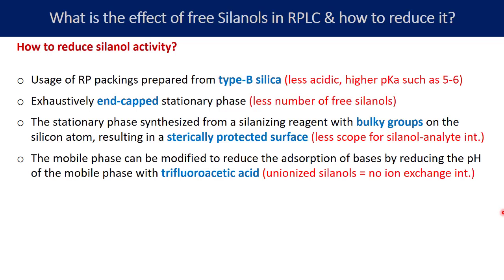Fourth, the mobile phase can be modified to reduce adsorption of bases by reducing the pH with trifluoroacetic acid. At very low pH — like pH 2 to 2.5, or below 3 — silanol groups remain unionized, preventing ion exchange interaction. So if your compound is interacting via ion exchange, you can use trifluoroacetic acid at lower pH to avoid the secondary silanol interaction.